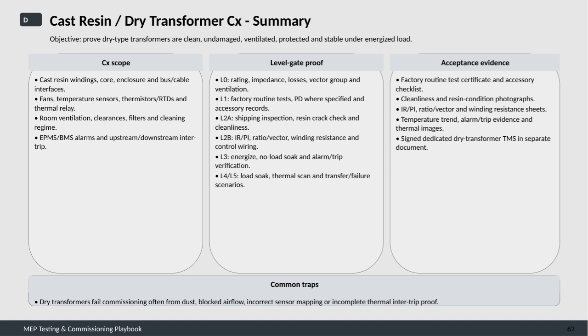Common pitfalls that many encounter during commissioning include dust contamination, blocked airflow, incorrect mapping of sensors, and incomplete proof of thermal inter-trip functions. Addressing these traps early is critical to a successful dry transformer commissioning.